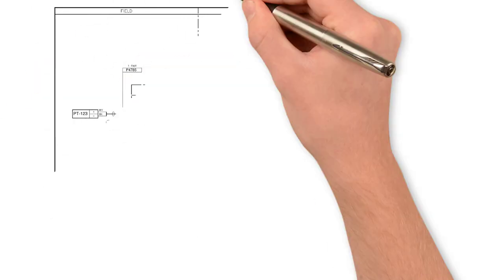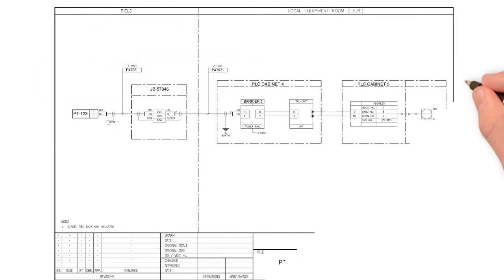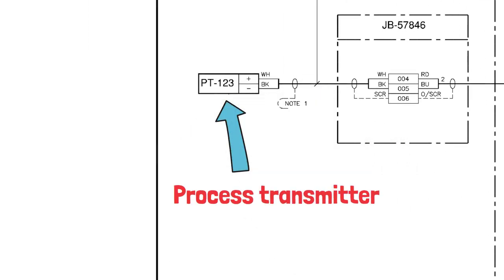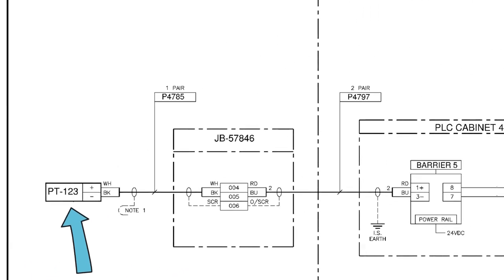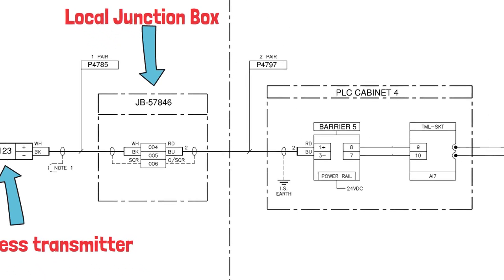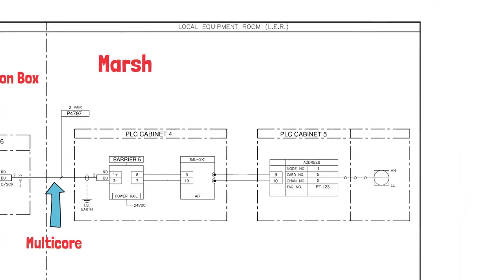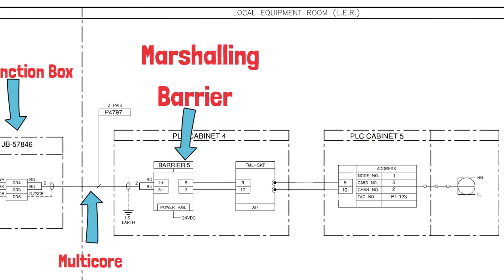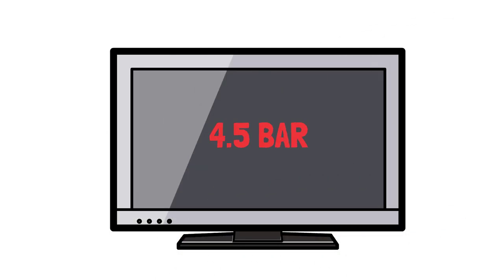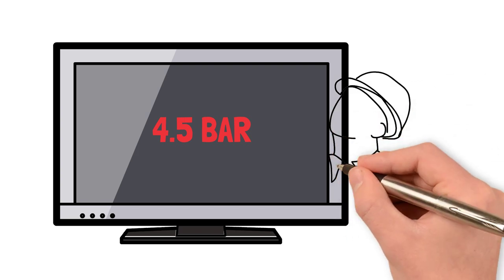Here is the configuration of the type of loop we'll be fault finding on. The field transmitter will be connected to the process, maybe by small bore tubing or directly in pipework or a vessel. The two-wire transmitter is going to pass through a local junction box and onto a multi-core back to a marshalling cabinet, likely in an equipment room. In the marshalling cabinet, the loop will have an input isolator or barrier, and then the loop will be terminated into a PLC input card. The process variable will then be displayed on an HMI, or human machine interface, that a plant operator will be monitoring.